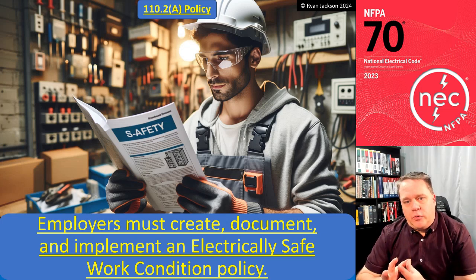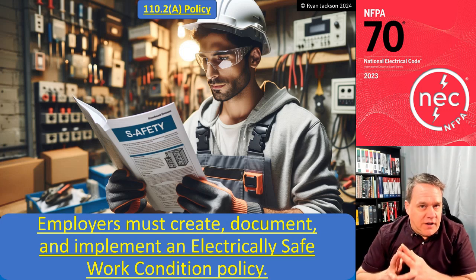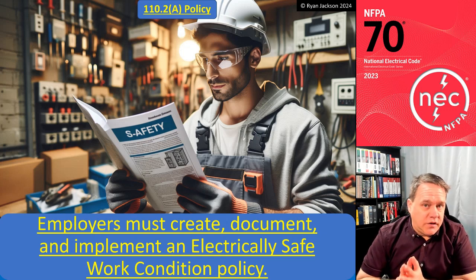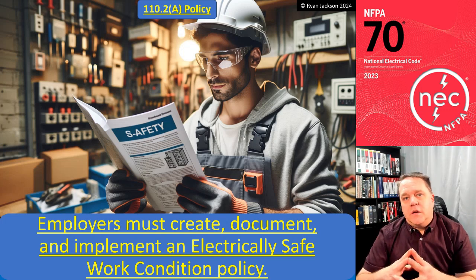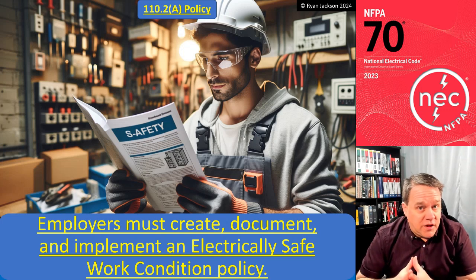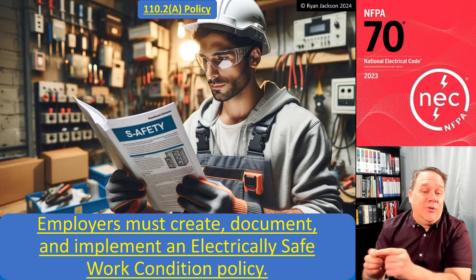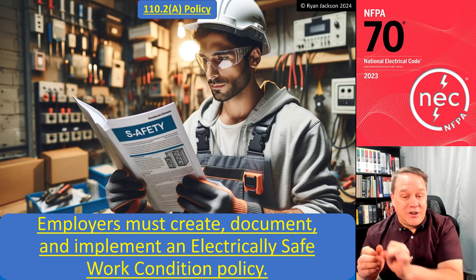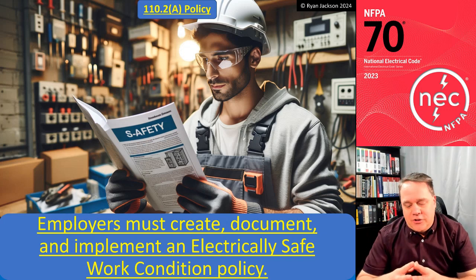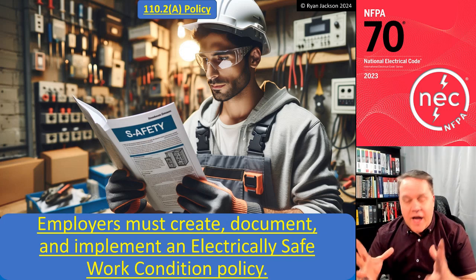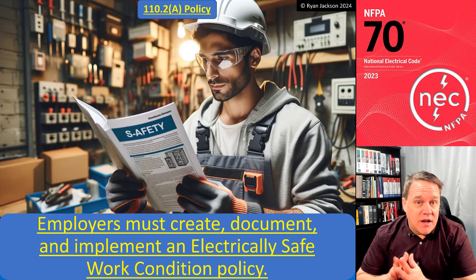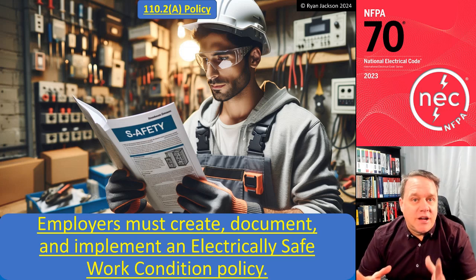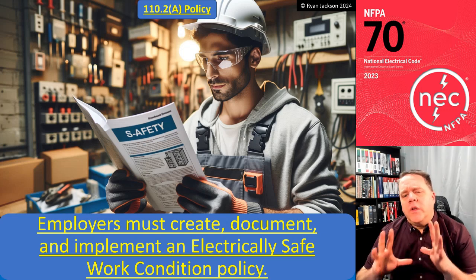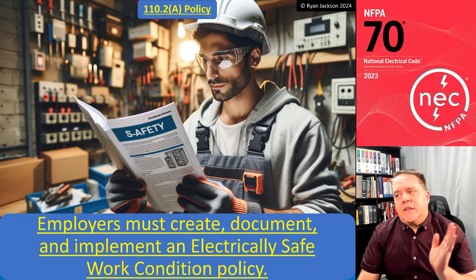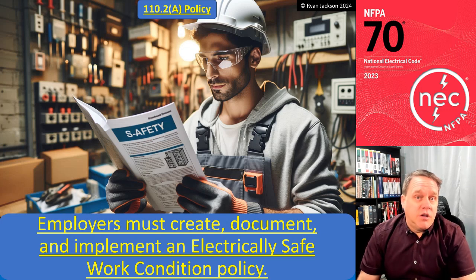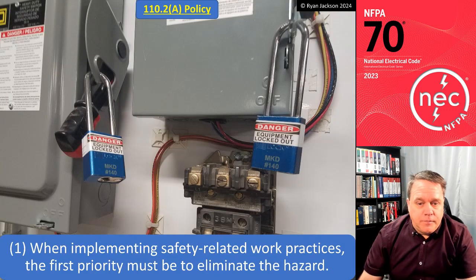Part of that program needs to include an electrically safe work condition policy, and that policy needs to include when you need to establish an electrically safe work condition. It'll talk about doing hazard analysis, whether we're talking about shock analysis, electric shock analysis, or arc flash risk assessments. So we need to create an electrically safe work condition policy, tell us how to create an electrically safe work condition, and when one is required.